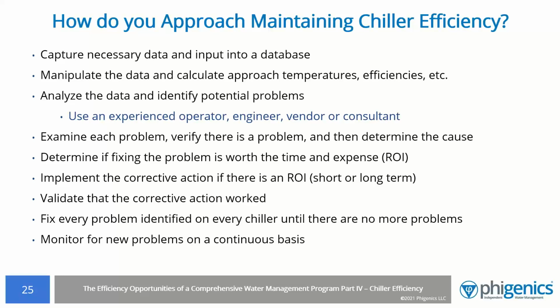Capture necessary data and input it into a database or a spreadsheet, but you've got to record it. Manipulate the data and calculate the approach temperatures, efficiencies, and other things. That's where your teenager and the algebra comes in. Then you need to analyze the data and identify the problems. Then you take each problem, verify that there is a problem, because it's not always the case that there is, and then determine the cause.